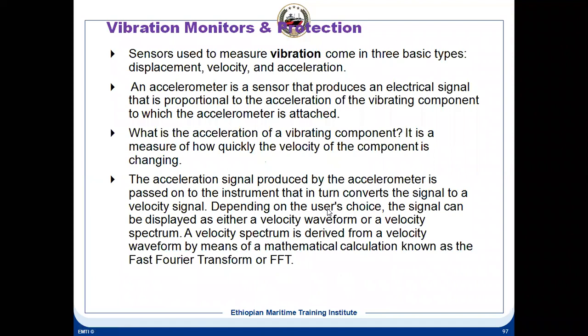So vibration comes in 3 basic types, that is displacement, velocity, acceleration. We measure the vibration basically in 3 places: horizontal, vertical, and axial. So these are the 3 places we take measurements: axial vibration, vertical vibration, horizontal vibration.